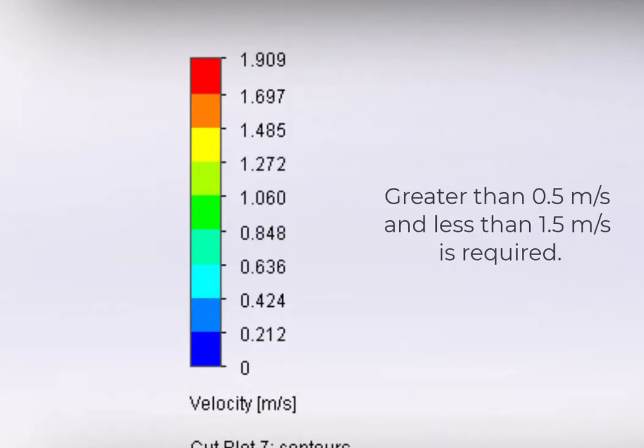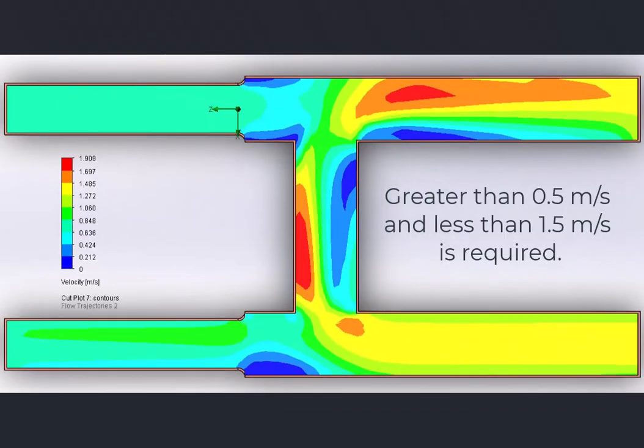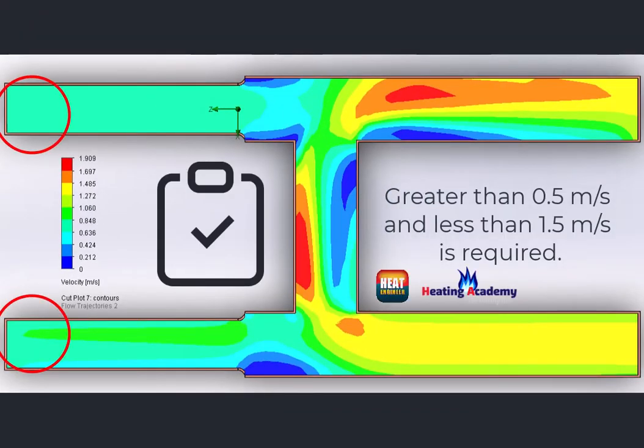So colours from light blue to yellow is what we really want to aim for from the flow return from the boiler and also the flow return from the underfloor heating system, which we've got here. So this is an acceptable velocity for this particular system.